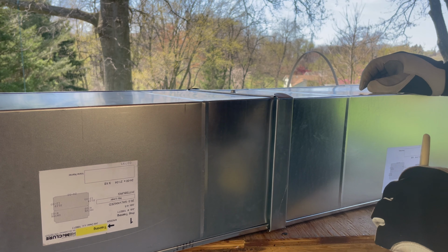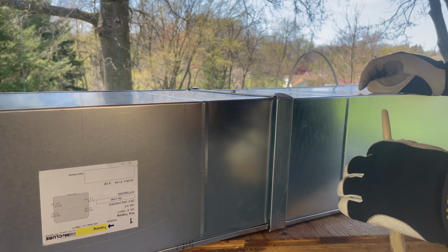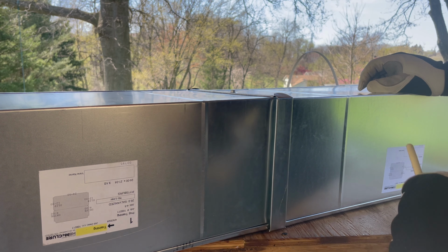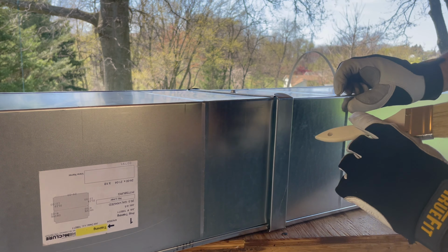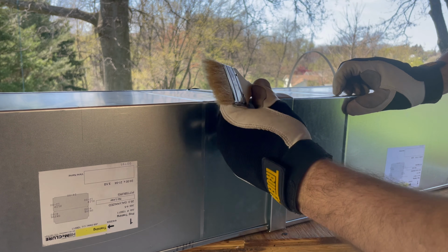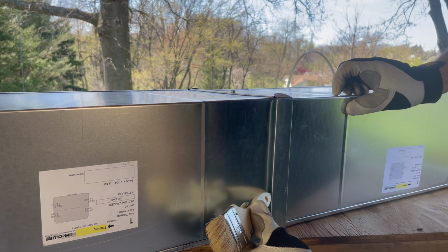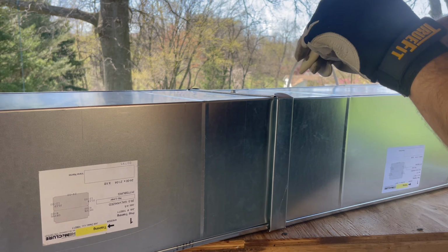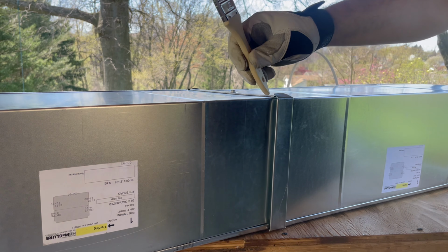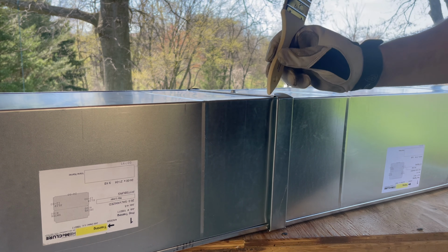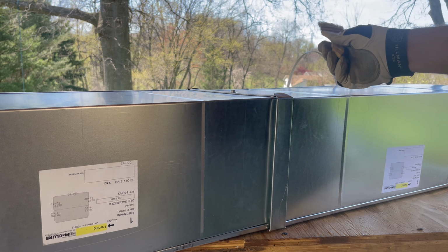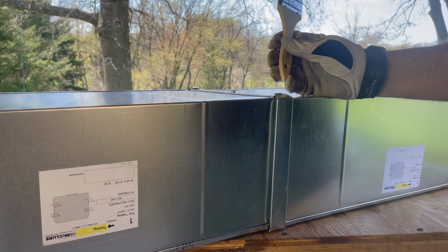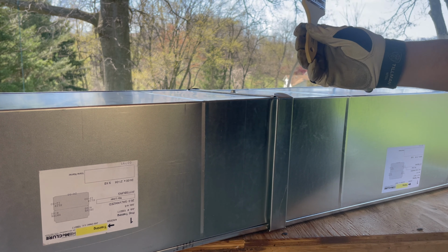First thing we're going to look at sealing here is this piece of slip and drive duct that we assembled in a previous video. Some of the crucial areas you've got to really make sure we're sealing are around these corners and on the inside of the drive. We want to make sure that we're doing a really good job with the slips as well, but your bigger gaps are going to be around your drive. When we're painting the duct seal on, you want to make sure it's at least 1/16 inch thick.